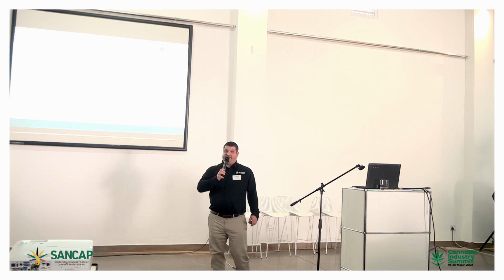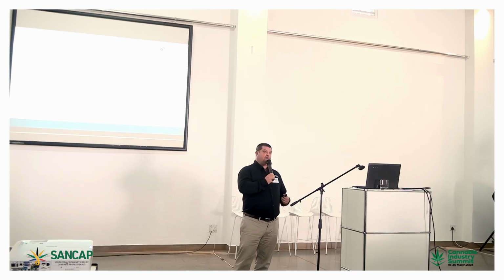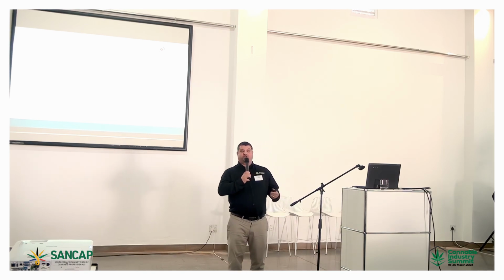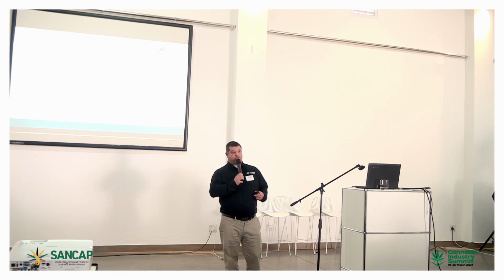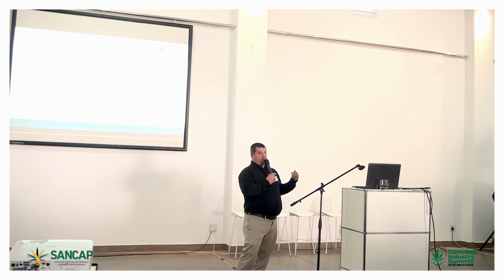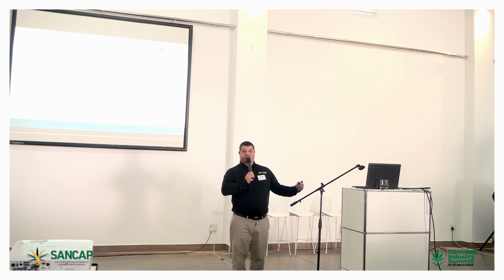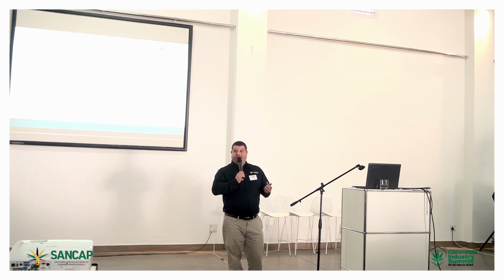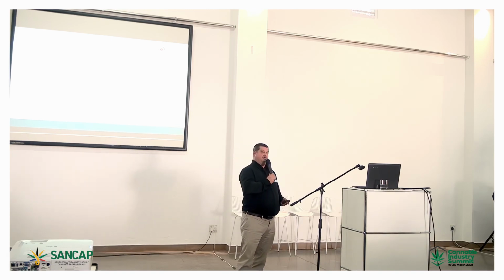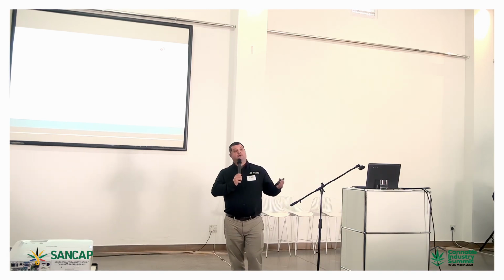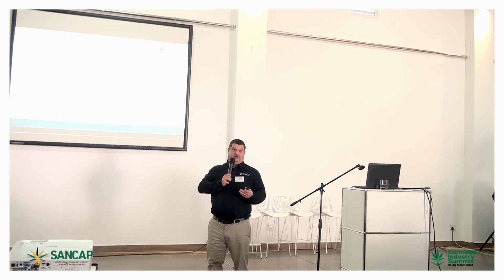Again, the drawback is efficiency. What you're doing here when you do reheat is trying to make your air conditioner do all your dehumidification. So when your air conditioner shuts off because you no longer need it for temperature, you fire up a heater to make the air conditioner run again so it can take out moisture, even though you don't need it for temperature.